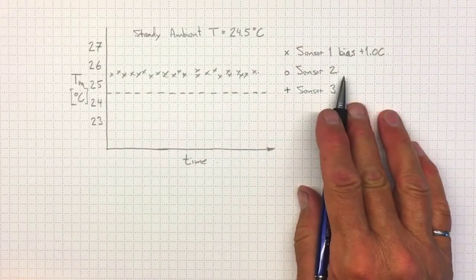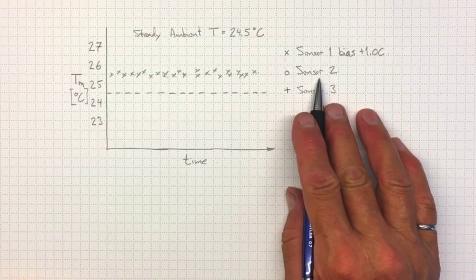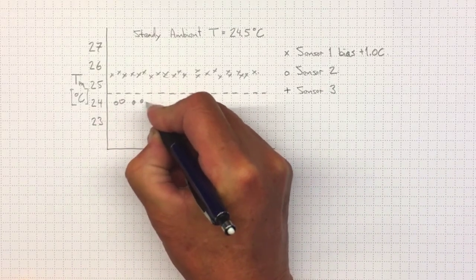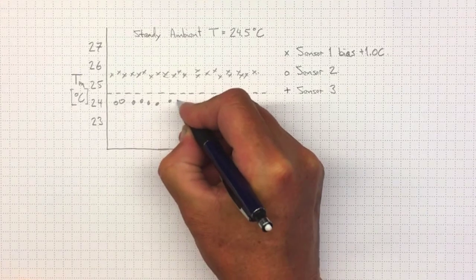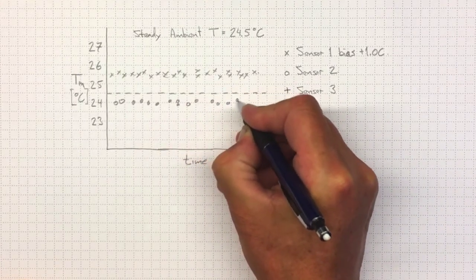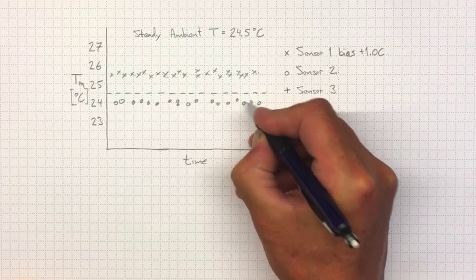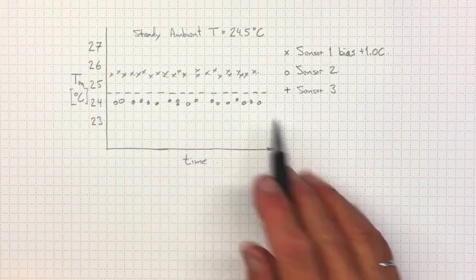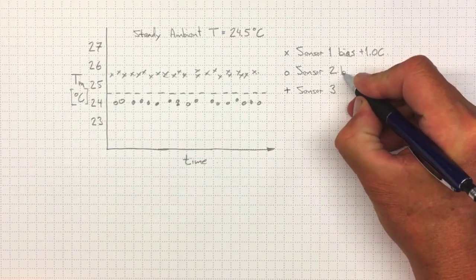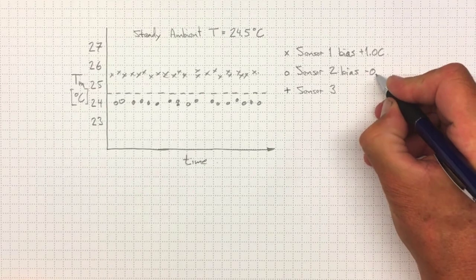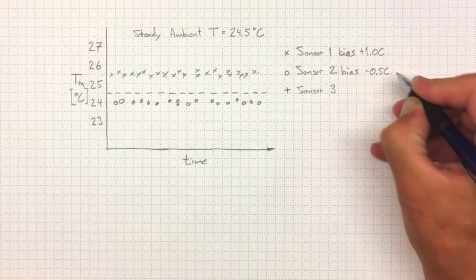I could repeat that test with sensor number two and I might wind up with a bunch of little circles like this over time. And that would tell me that sensor number two has a bias of about negative a half a degree C.